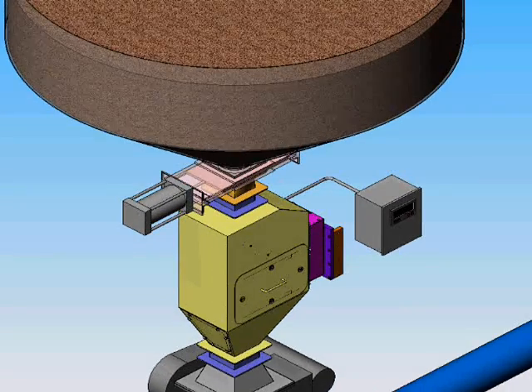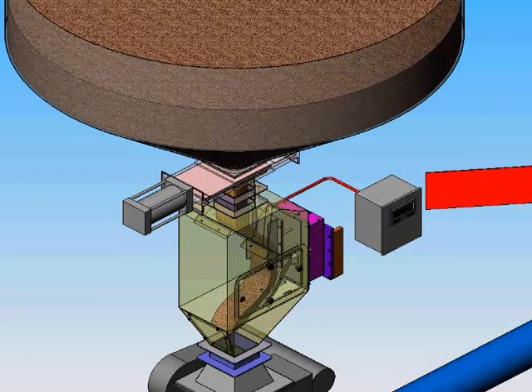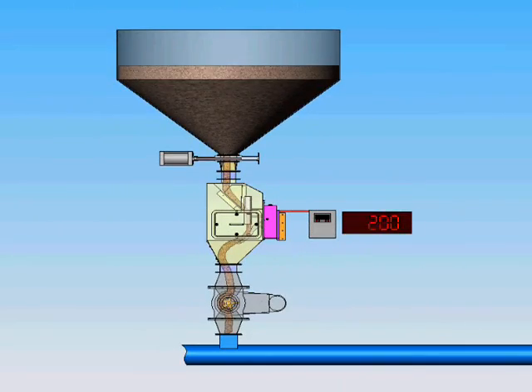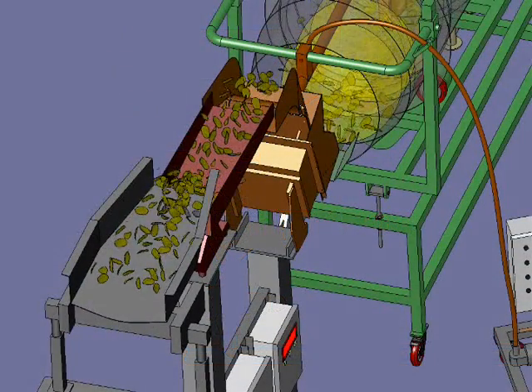The Centriflow Meter provides two outputs: a pulse output and a flow control output. The pulse output is a totalizer output that sends out 500 pulses per second. This pulse count, plus the 100 millisecond time constant, means greater signal resolution, which means superior accuracy. This totalizing allows the meter to be used for batching, filling, and inventory control.